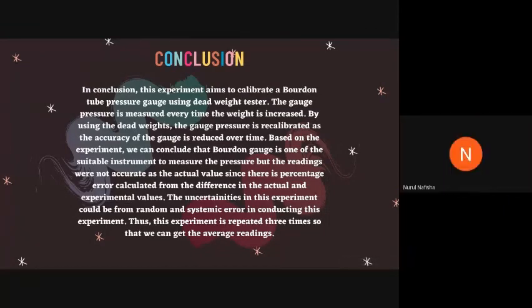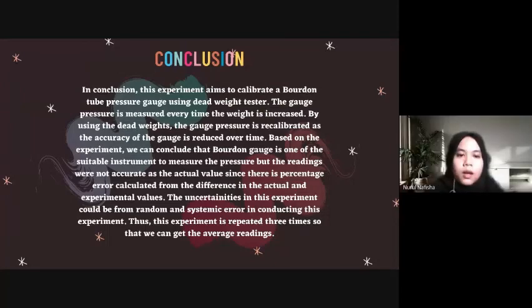So for the conclusion, this experiment aims to calibrate a Bourdon tube pressure gauge using a dead weight tester. The gauge pressure is measured every time the weight is increased. By using the dead weights, the gauge pressure is recalibrated as the accuracy of the gauge is reduced over time.